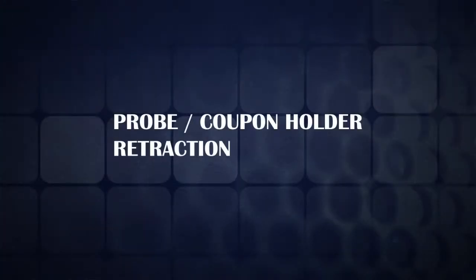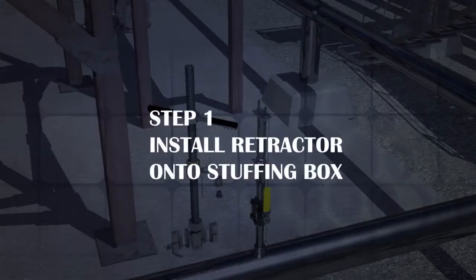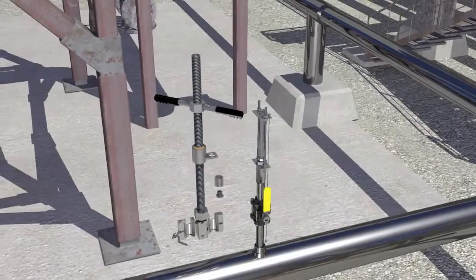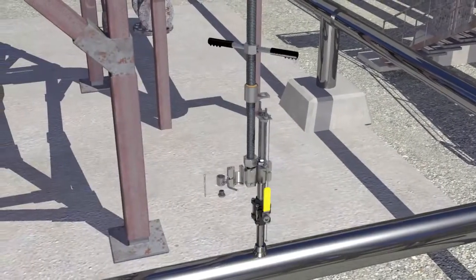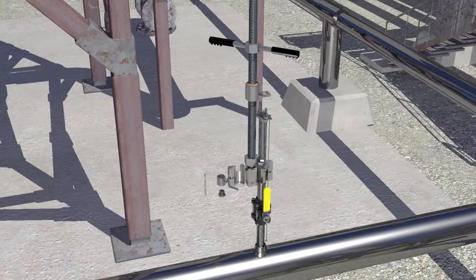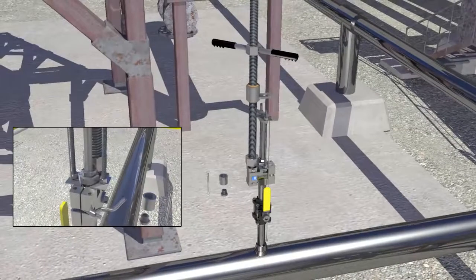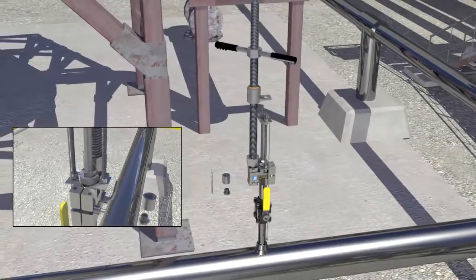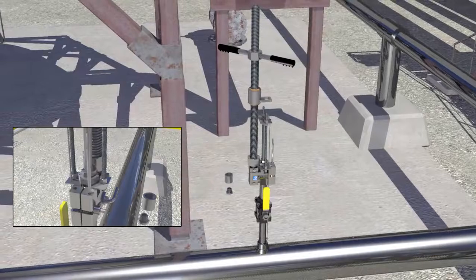Probe coupon holder retraction. Step 1. Install retractor onto stuffing box. Assemble the two halves of the clamp assembly around the probe stuffing box such that the cutout in the clamp aligns with threaded rods, when present, and ensuring the safety cable is not crossed or interfering, draw the clamp assembly together and secure with the lever nut. Insert the quick release pin into the hole provided on the right half of the clamp assembly.